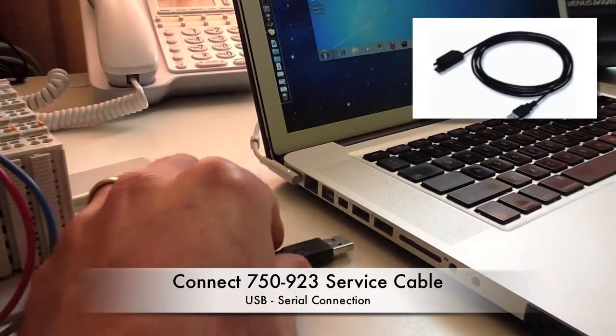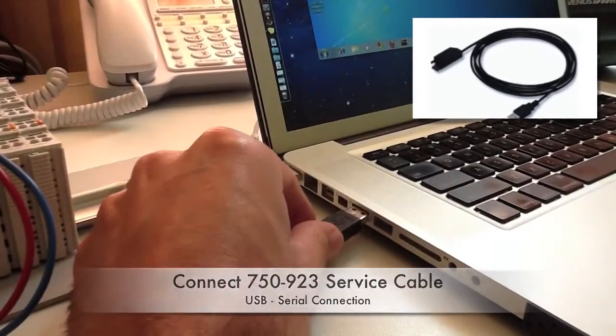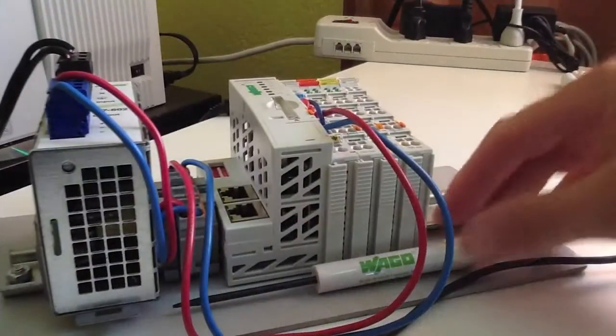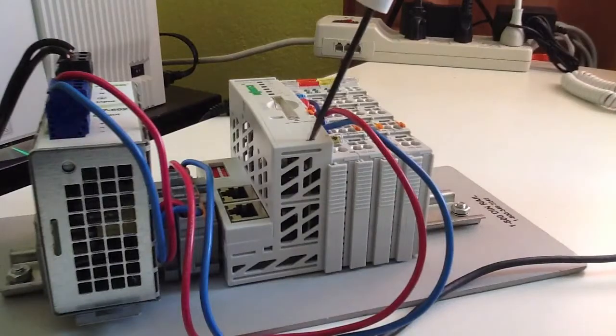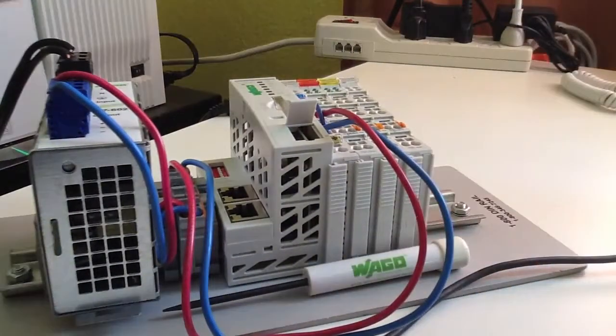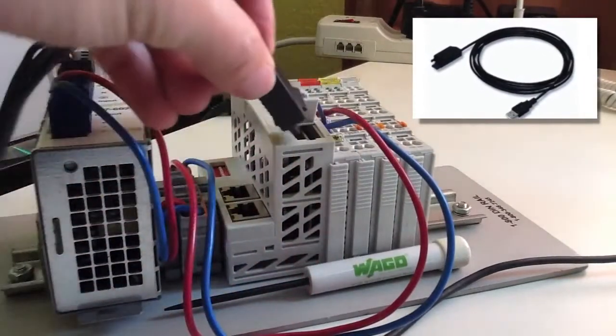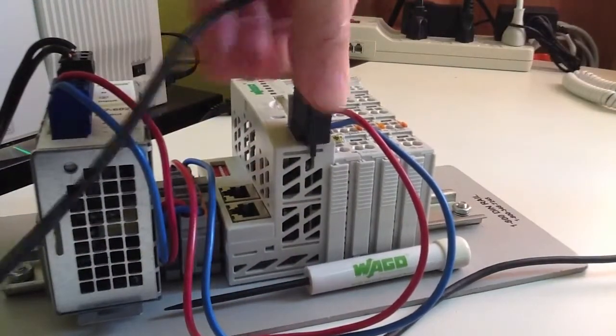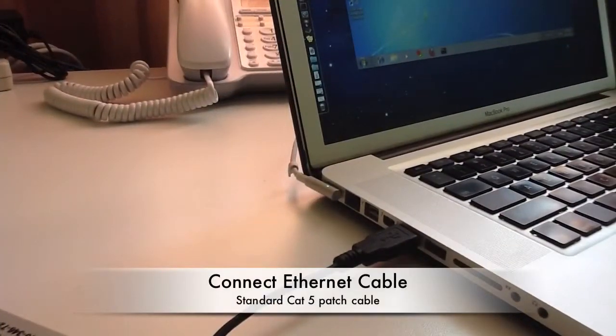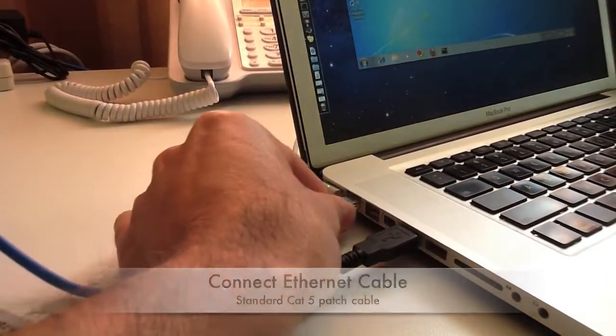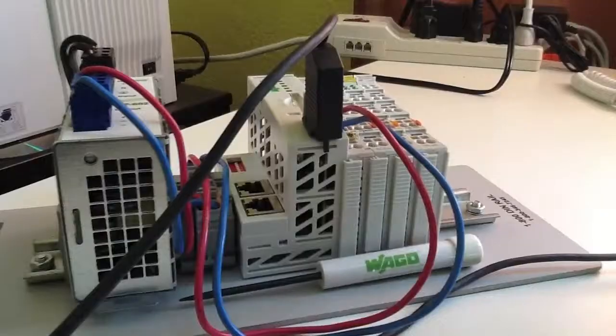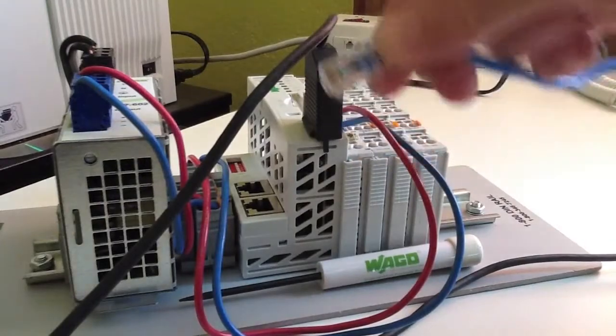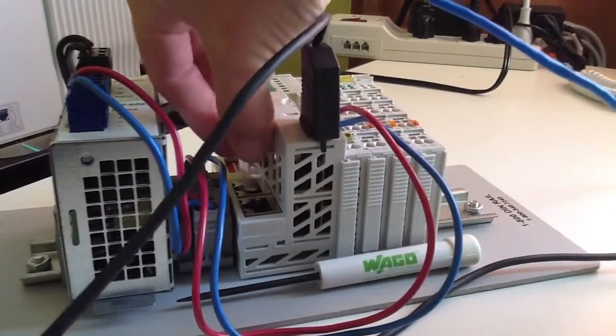We're now ready to connect the 750-923 service cable into the USB port of your computer, and then using a screwdriver, open up the trapdoor that conceals the serial cable connection, and go ahead and connect the other end of that cable to the PLC. You also want to connect a standard Cat5 patch cable from your computer into the PLC's Ethernet port.